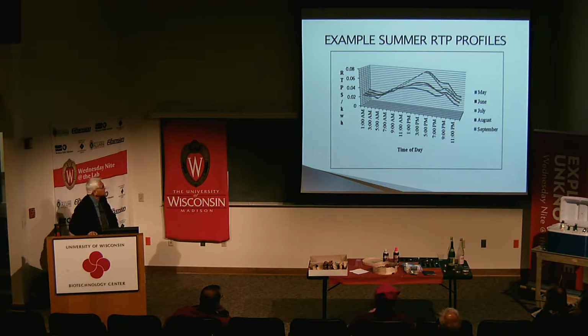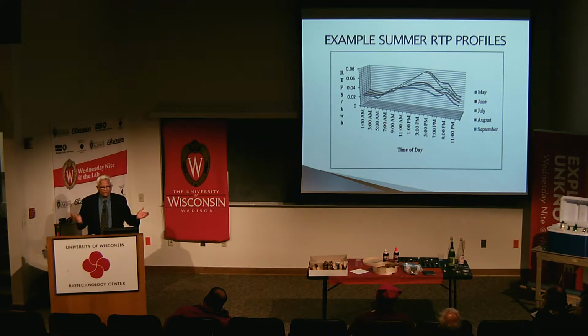on energy cost. Not only that, if you can shift even some of the loads which are in this zone to a lower cost area even during the on-peak, you can save some energy costs. Now, I have not included the demand charge in this because the demand charge is based on the entire building system load. And in this case, I'm considering just HVAC and lighting. And this type of RTP profile comes every day of the year, and it's available to the customer one day ahead of time, maybe around 4 o'clock the previous day. It is communicated to the smart building facility management system.